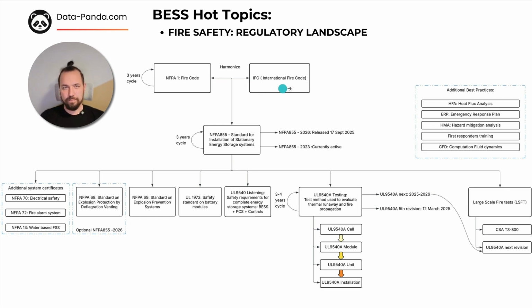At the top level, we have the main fire codes used by authorities having jurisdiction. The first is NFPA 1. It's the fire code developed by the National Fire Protection Association, so it's for North America. The second is the International Fire Code, or IFC, developed by the International Code Council. These two codes are updated roughly every 3 years and are continuously harmonized, so that fire safety requirements remain consistent across different jurisdictions. So fire code NFPA 1, it's US based, is developed based on IFC.